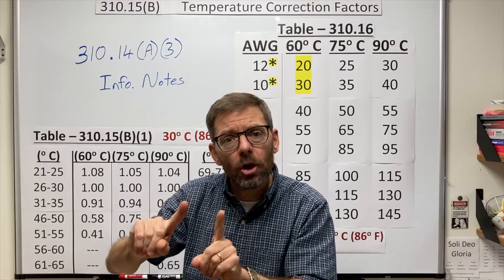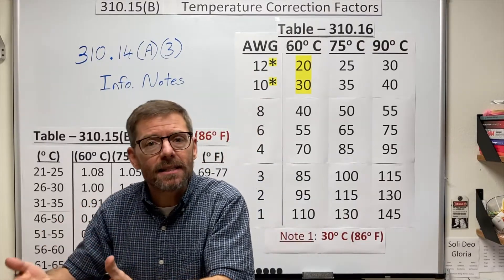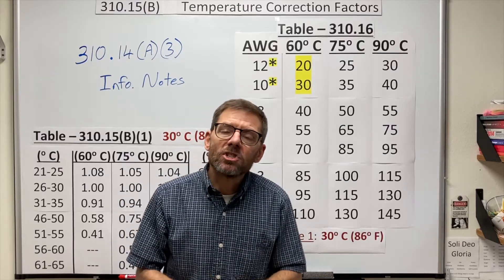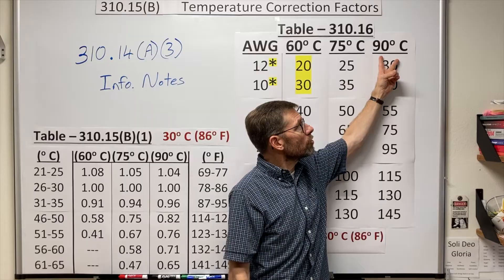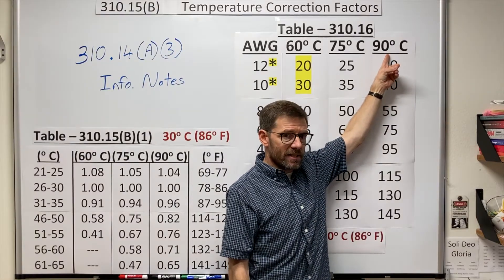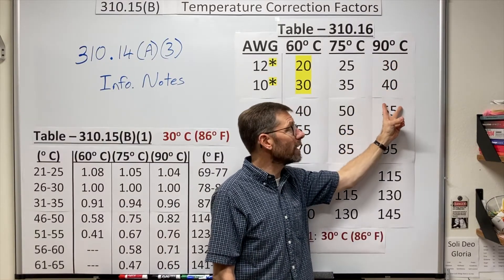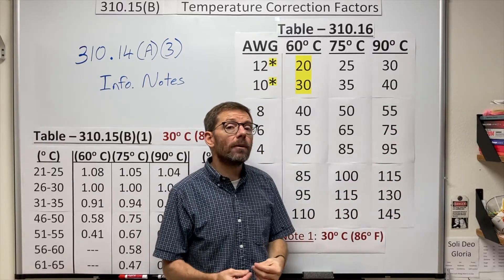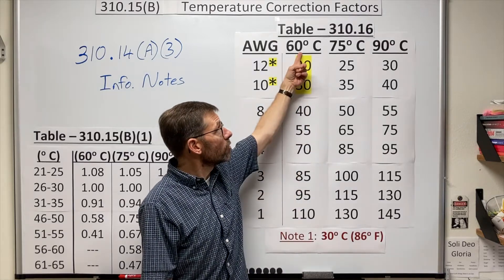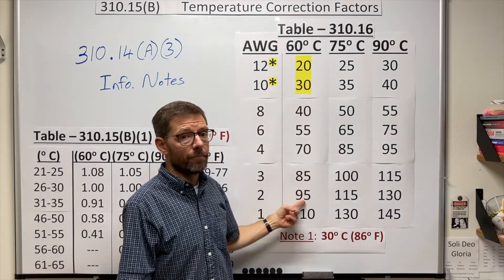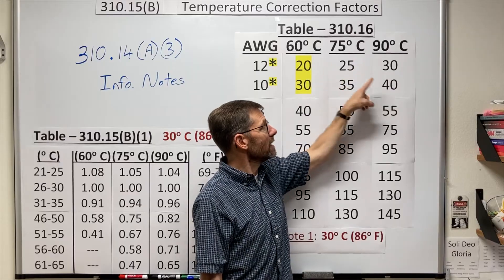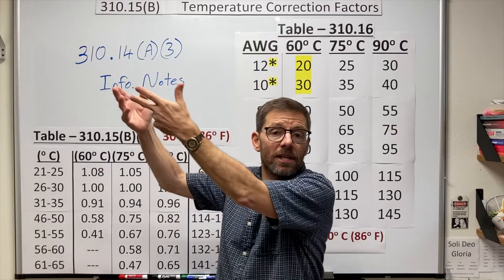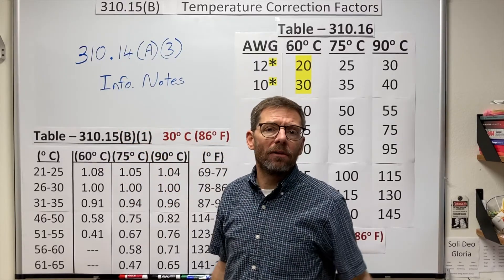Here's a quick note on residential attics. In residences, you're often using Romex or NM cable, which has an interesting quality — it's constructed to the 90 degrees Celsius rating, so I can start my calculations with those ampacities. However, I can never run more amps on it than those in the 60-degree column. So that reduction in ampacity is often enough to accommodate your attic temperatures, especially if they're well ventilated.